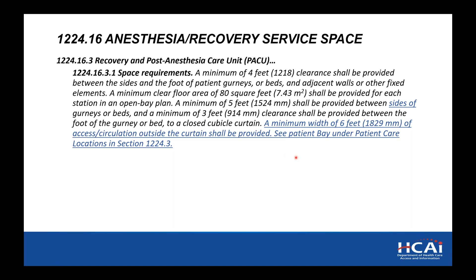And then we go on to add the language, a minimum width of 6 feet of access circulation outside the curtain shall be provided. And then it just points to the patient bay under patient care locations under the definitions for a patient care station, cubicle, and a bay. But the 6 feet is required outside the cubicle curtain. And it says access and circulation because it's not always necessary at the foot of the bed. It may be at the side of the bed, but 6 feet between cubicle curtains is required. And again, you'll see this repeated in several sections that have the same requirements.